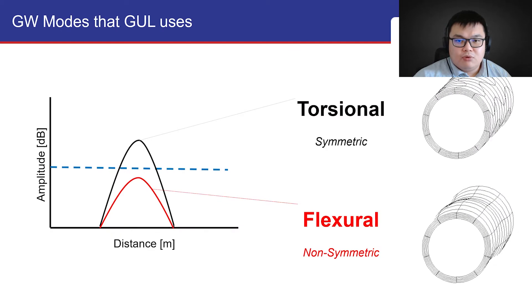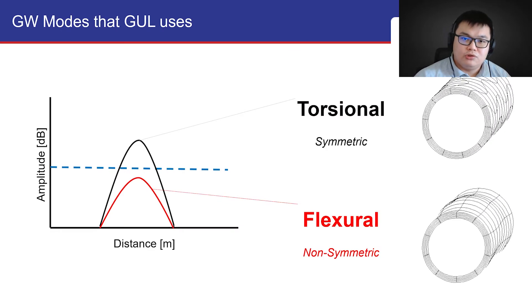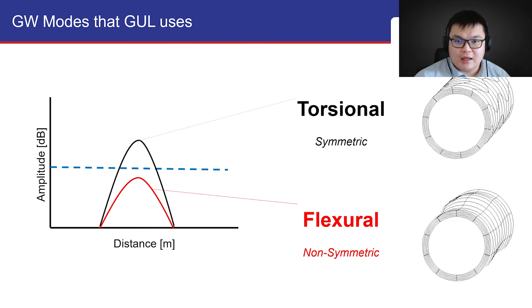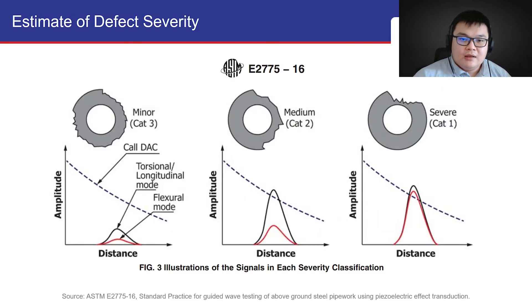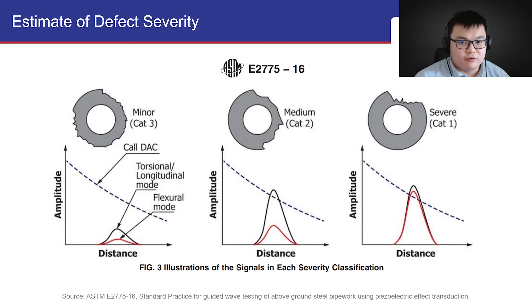The GuidedWave modes that GUL uses are the torsional and flexural modes, which are represented by the black and red signals on the A-scan, respectively. The severity of the defect can be estimated by the amplitude of the black and red signals relative to the call DAC. For more information, you can refer to international standards such as ASTM E2775-16.